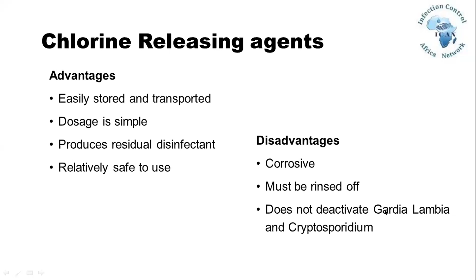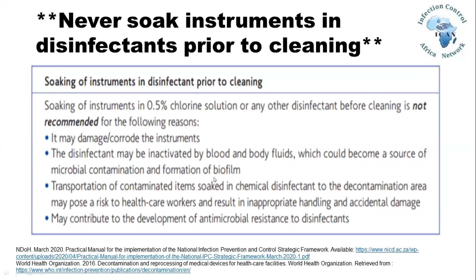We know never to soak instruments in disinfectants prior to cleaning, because this can damage or corrode the instrument. The disinfectant might be inactivated by the blood and body fluids. Transportation of the contaminated items soaked in chemicals to the decon area may pose a risk to the healthcare worker and may contribute to development of antimicrobial resistance. Then the last area we're going to be looking at is sterilization. And there you see there's a couple of autoclaves and benchtop sterilizers that one might use.